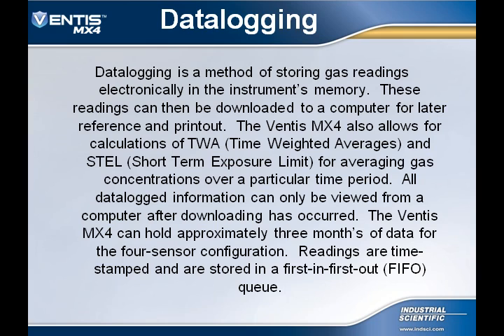The Ventis MX4 can hold approximately 3 months of data for a 4-gas configuration. Readings are time-stamped and are stored in a first-in, first-out FIFO queue.